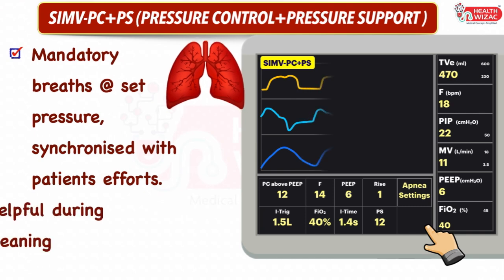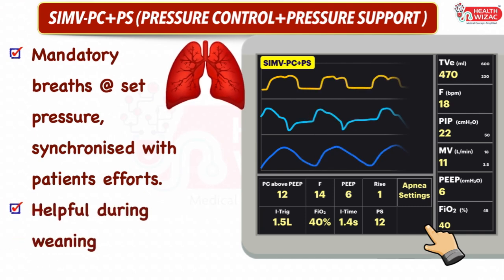Next is SIMV pressure control plus pressure support mode. In this mode we have to set PC above PEEP, frequency, PEEP, rise time, inspiratory trigger, FiO2, inspiratory time, pressure support settings, and apnea settings for backup ventilation. In this mode, the ventilator delivers mandatory breaths at set pressure which are synchronized with the patient's spontaneous efforts.